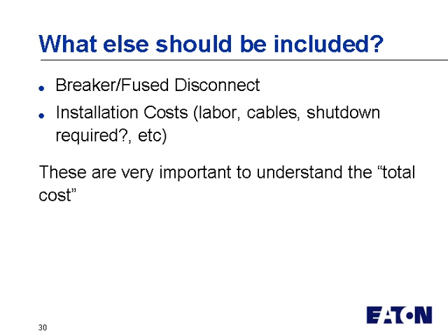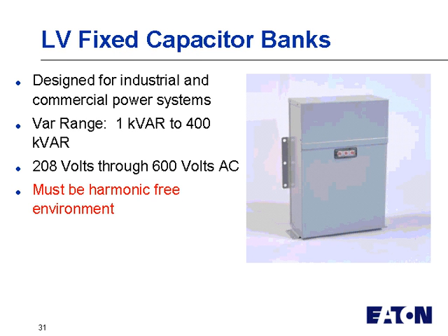What else should be included? And I like to tell people that if you only look at the cost of the capacitor or harmonic filter, then you're really missing the true return on investment. You really have to think about what's the breaker or fuse disconnect that I'm going to use to feed this thing. And then what's the installation cost? Is there labor involved, cable shutdown? These are very important to understand the total cost. If you leave these out, your return on investment may look a lot sooner than it really may be, and we don't want to try to fool anybody.